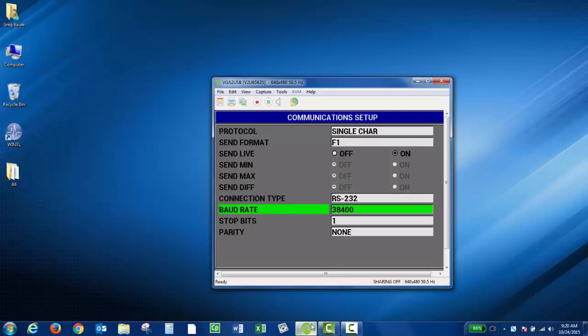From here you can choose your baud rate, your stop bits, your parity. If you're interfacing to a non-Olympus program that might require certain comm settings you can make your adjustments here. For demo purposes I'm going to just change my baud rate to 9600 and then press the measure key.